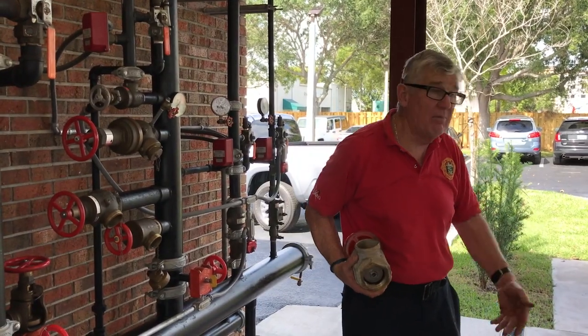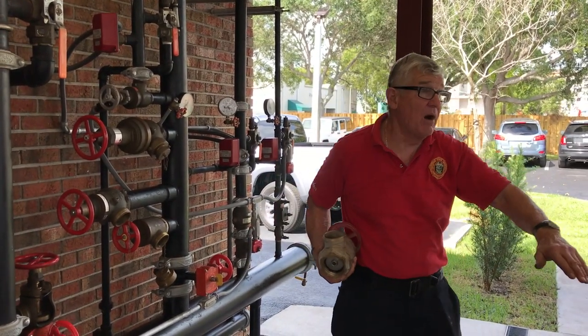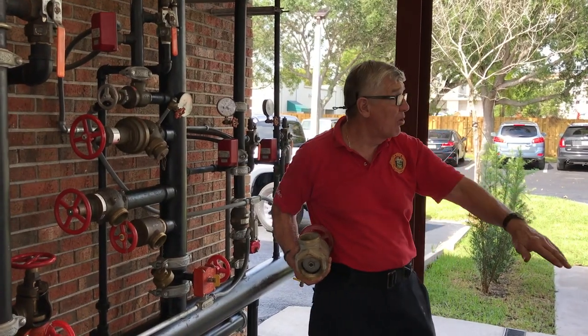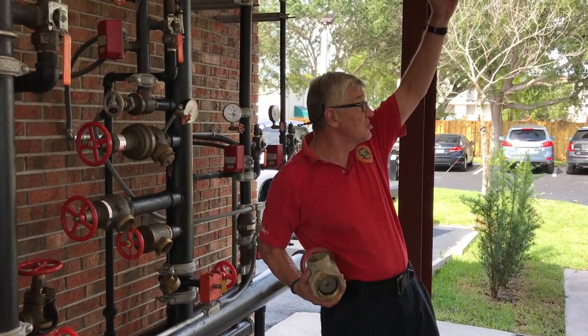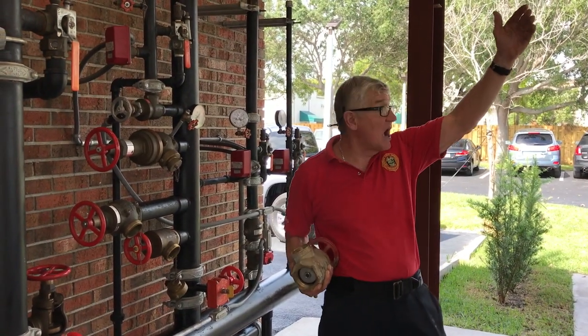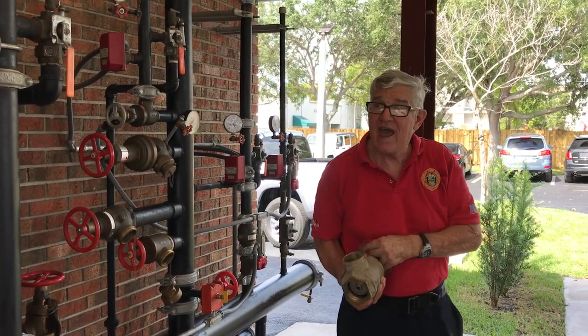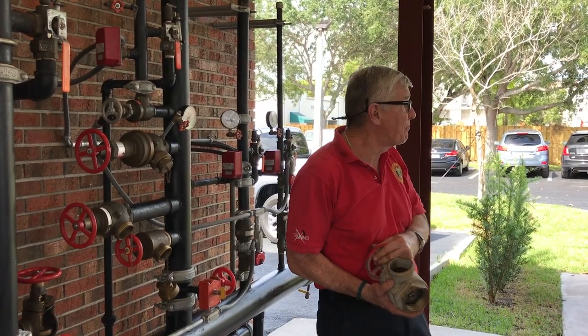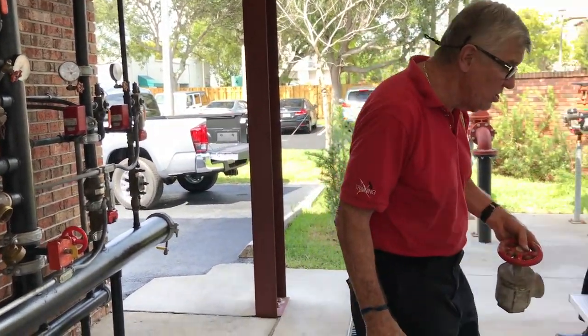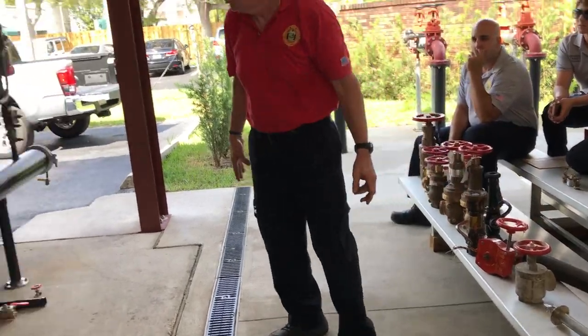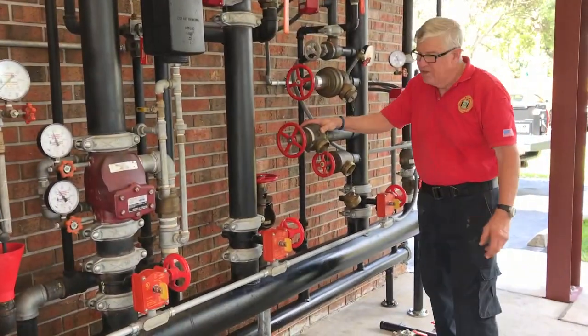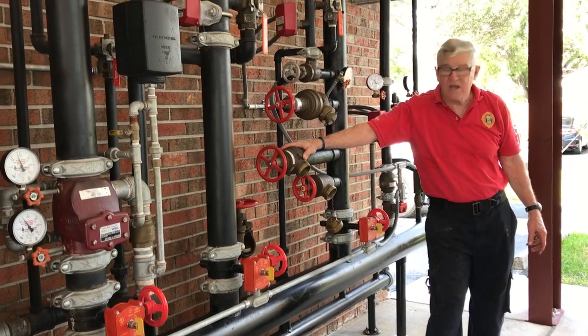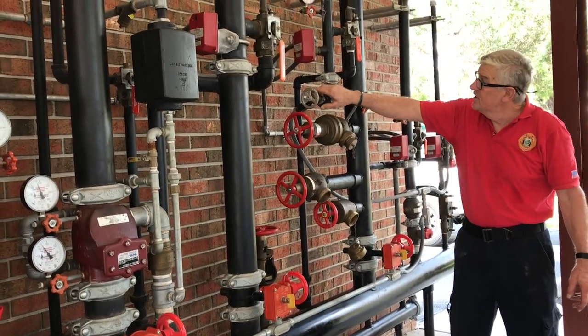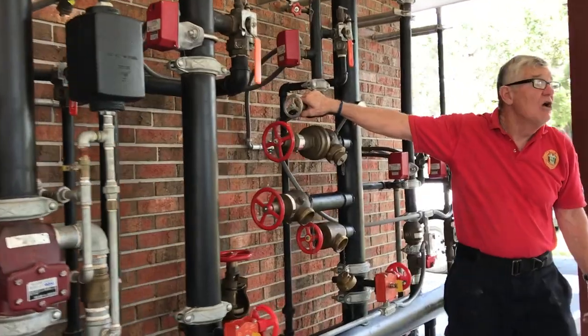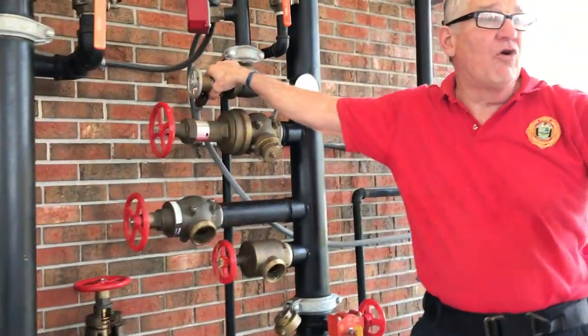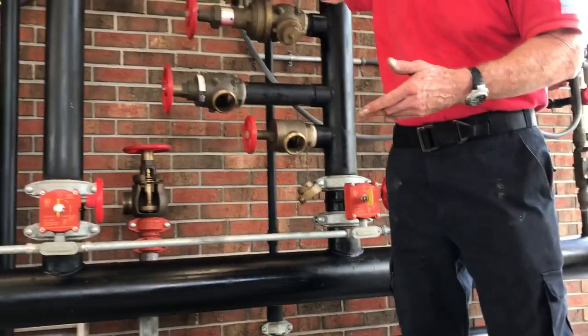Where does this get to be a problem? In a very tall building, because your fire pump is going to have to generate a heck of a lot more pressure than 175 to achieve a flow of 100 PSI at the roof. So we have to have some way of controlling that pressure, of reducing that pressure. We do that with a pressure reducing valve. This is a pressure reducing hose outlet valve. This is a pressure reducing sprinkler control valve or zone control valve.